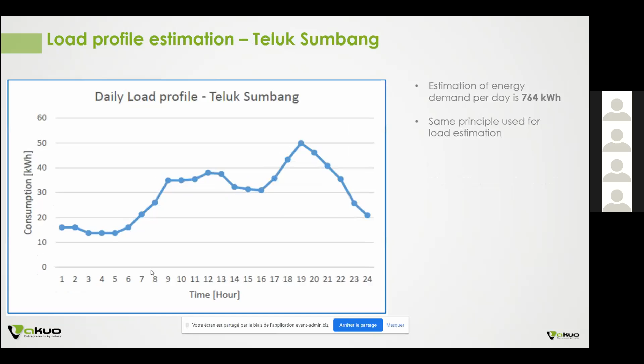One of the requirements, specifically from the MCA, was to design the mini grids for year 20. That's a critical question mini grid developers must have in mind: when does the mini grid become too small for the expected demand growth. The requirement was to develop for year 20, leaving plenty of time for future expansion. Looking at national demand growth across Indonesia, it's roughly 3%. Here we expected 6% growth for the first 5 years, with usage increasing faster as they gain access to 24/7 electricity, and eventually demand growth slowing down to reach the national average.